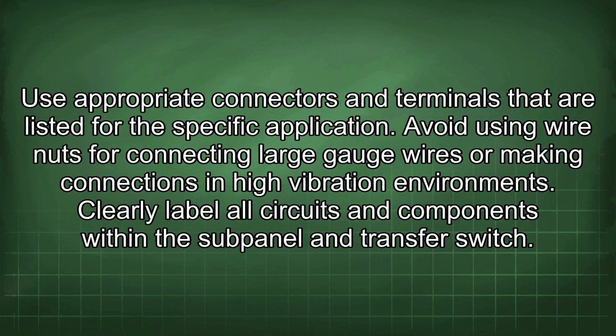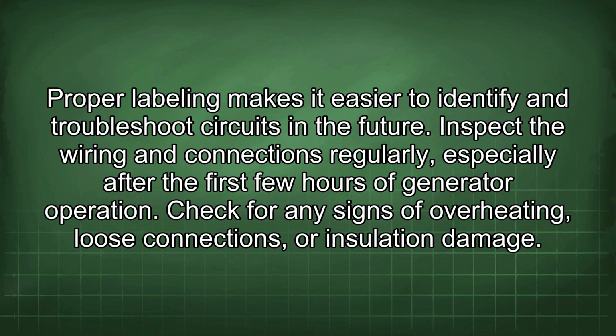Use appropriate connectors and terminals that are listed for the specific application. Avoid using wire nuts for connecting large gauge wires or making connections in high vibration environments. Clearly label all circuits and components within the subpanel and transfer switch. Proper labeling makes it easier to identify and troubleshoot circuits in the future.